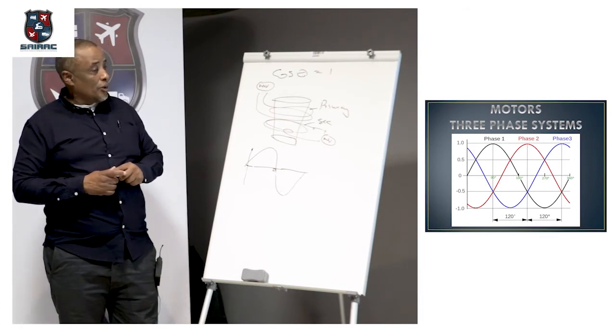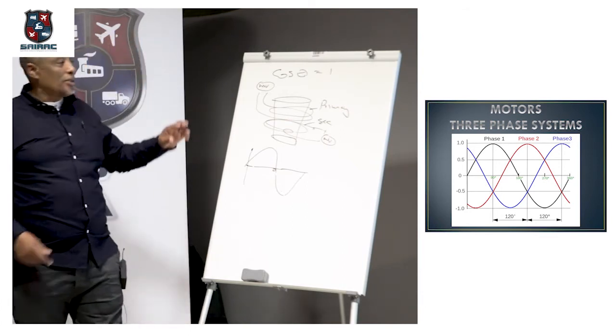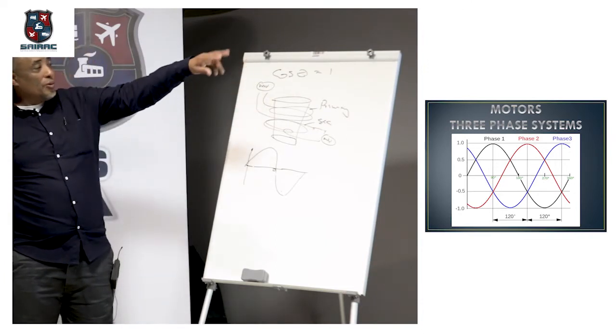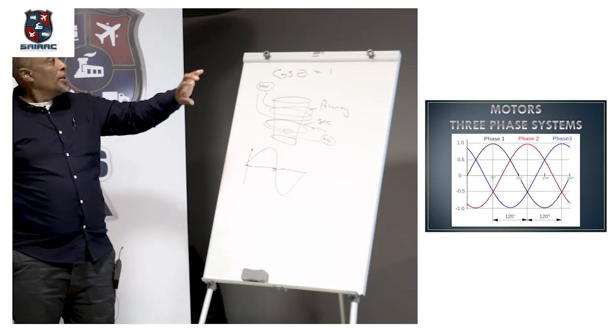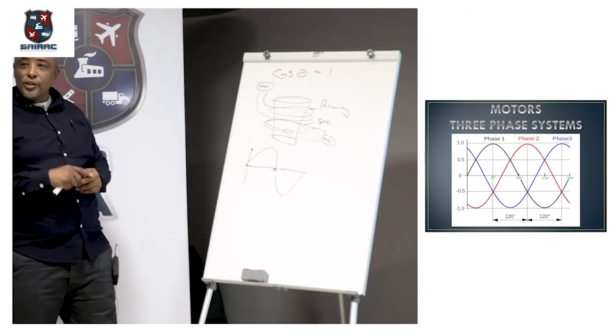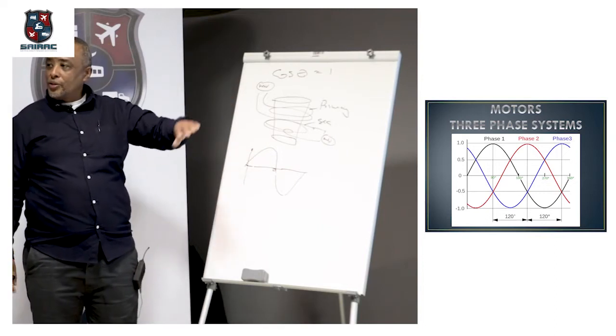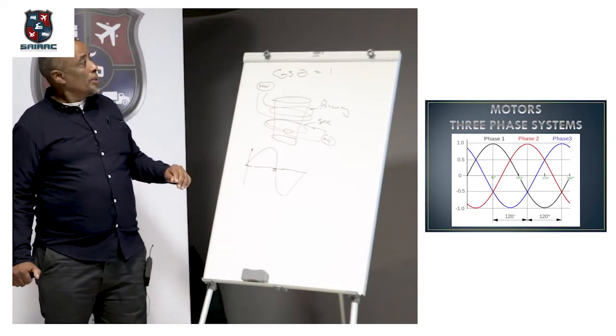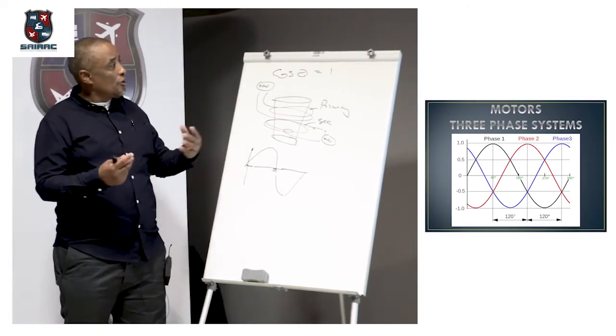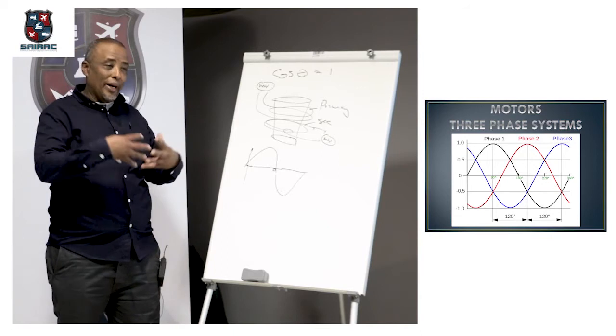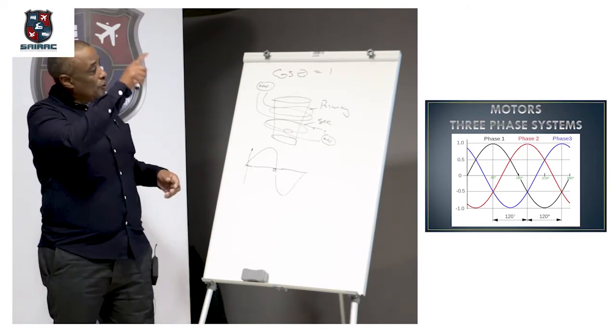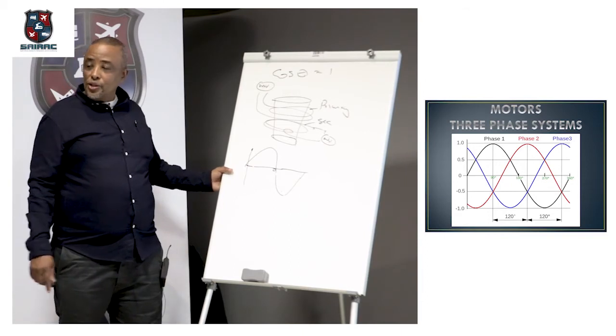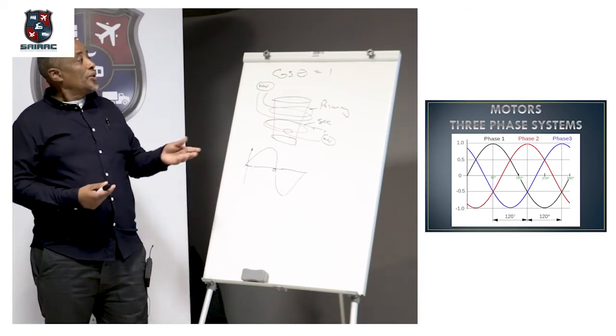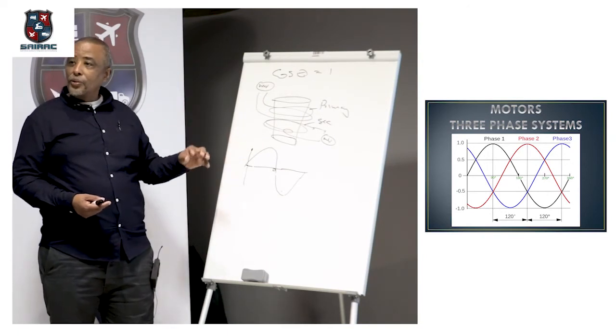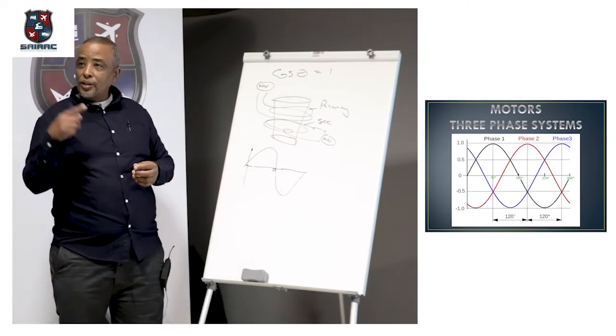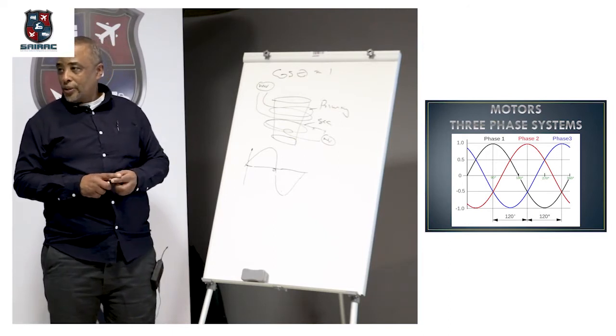Okay, now let's discuss a motor. A motor consists of 3 sets of windings displaced at 120 degrees, electrical degrees apart. Each of these windings, when we energize the motor, will carry equal amounts of current. This current flowing through the windings creates magnetic fields. The magnetic fields combine to form what we call a resultant flux, which moves around the stator frame at a constant speed. This rotating magnetic field links with the rotor, which is now the secondary, and a force is exerted onto the rotor, and the rotor will turn in the direction of the rotating magnetic field. That's how a motor works.